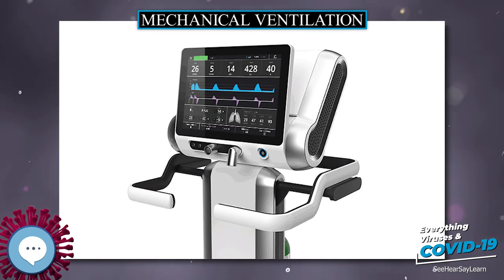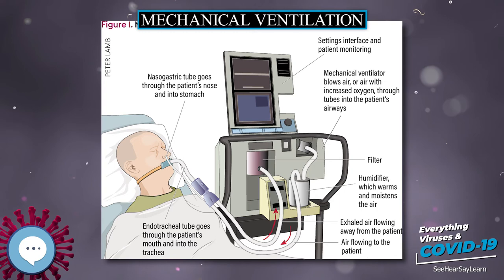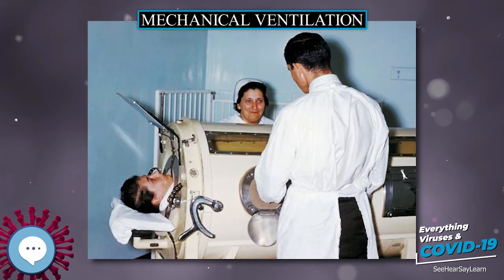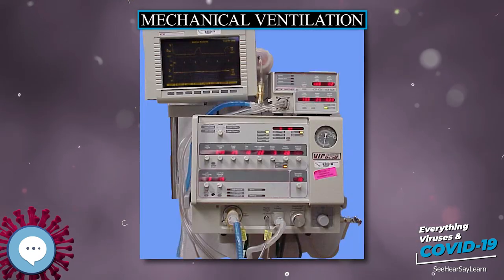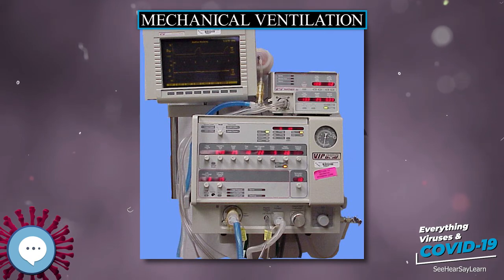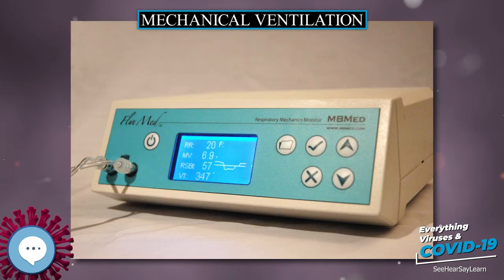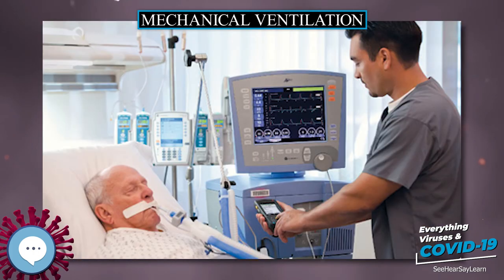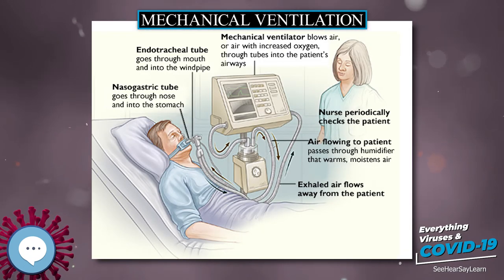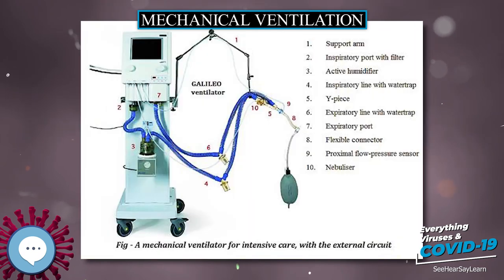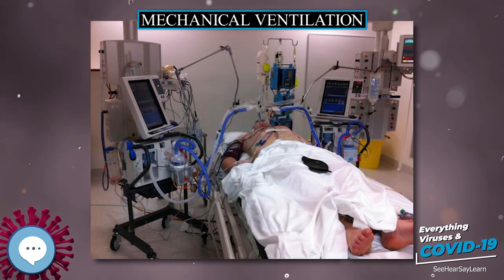The trigger is what causes a breath to be delivered by a mechanical ventilator. Breaths may be triggered by a patient taking their own breath, a ventilator operator pressing a manual breath button, or by the ventilator based on the set breath rate and mode of ventilation. The cycle is what causes the breath to transition from the inspiratory phase to the exhalation phase. Breaths may be cycled by a mechanical ventilator when a set time has been reached, or when a preset flow or percentage of the maximum flow delivered during a breath is reached. Breaths can also be cycled when an alarm condition such as a high pressure limit has been reached, which is a primary strategy in pressure-regulated volume control.